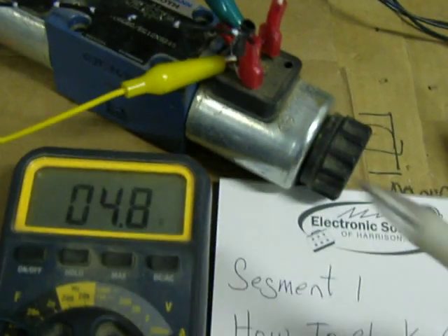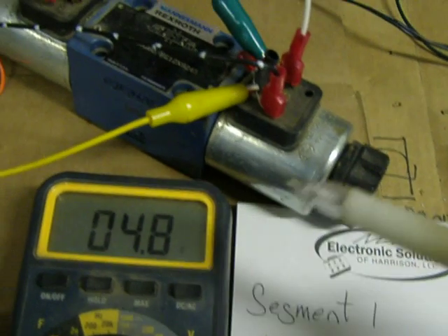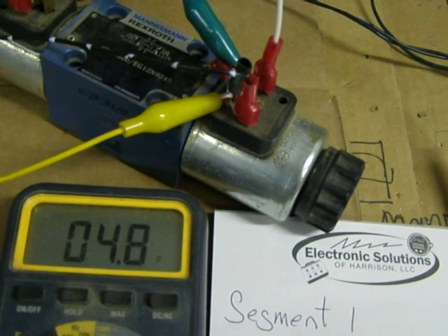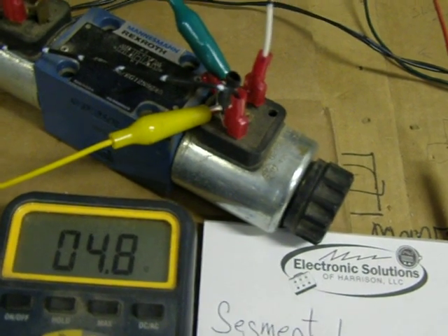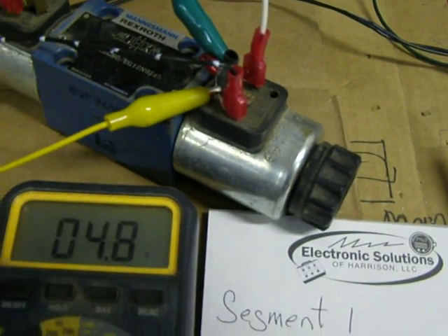So when in doubt, check it with an ohm meter, check it with an amp test, put an inline amp meter in line with it. Should only draw 2.5 amps. Check it on the machine side. If you've got any questions, give me a call. I'll be glad to help you. Thanks. See ya.